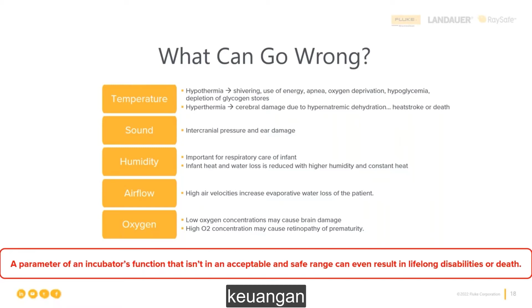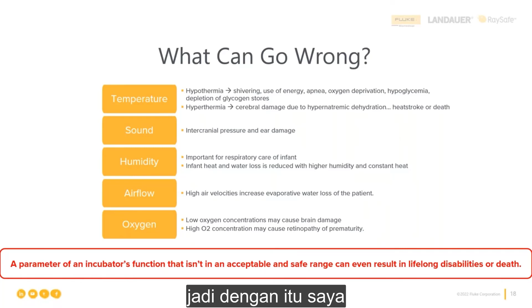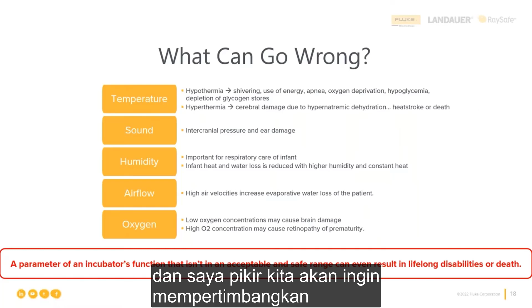And if we can test incubators and help ensure that they're functioning the way that they should be, we can help eliminate any time that's spent in the unit due to faulty performance of the incubator, and needing to spend more time than they need to. So with that, I'll stop tugging on your heartstrings. And I think we will want to consider some other perspectives and reasons for why testing incubators, and doing so thoroughly, is so important.